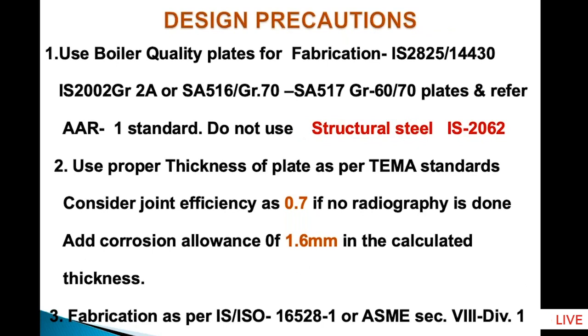What are the fabrication standards? Use of boiler quality plates, IS 2825 or IS 14430 or IS 2002 grade 2A is very, very important, or SA 516 grade 70. Most of the Indian manufacturers of ammonia plants today, to save cost, use IS 2062. IS 2062 is a structural quality steel and is not meant for pressure vessels, and therefore a lot of accidents take place. The cracking takes place because IS 2062 plates have higher carbon content, and my sincere request is, don't use it. Use boiler quality plates, and this is covered in our AAR standard.